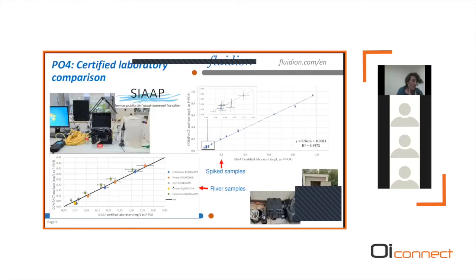So the SIAAP is a public wastewater utility of the Greater Paris area, and they have several monitoring stations all around Paris on different rivers to monitor the quality of the water. And we've done some intercomparison with their certified lab with the orthophosphate instruments. And you can see here on this graph that we got a very good intercomparison between our instruments and their lab, even at a low concentration as observed in the river around Paris. So our orthophosphate analyzer has been validated, its methodology has been validated, and now it's been installed at a river station from the SIAAP here on the Seine River, and it's currently being deployed.